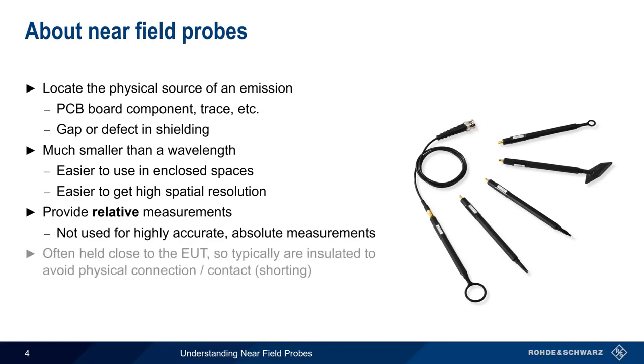Note, however, that near field probes are generally used for relative measurements, rather than for highly accurate absolute measurements of the received signals. And because they're used in close proximity to the EUT, they typically are insulated, to prevent electrical contact with the EUT, and avoid shorts and other associated issues. And finally, in some cases, near field probes are also used to inject, or to radiate signals into the EUT, but we won't be covering this topic in our presentation.